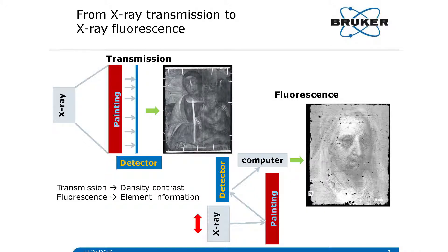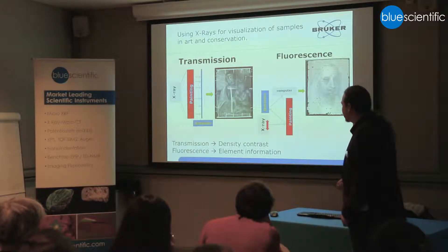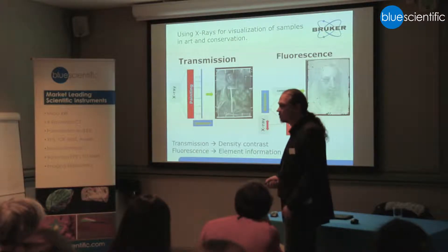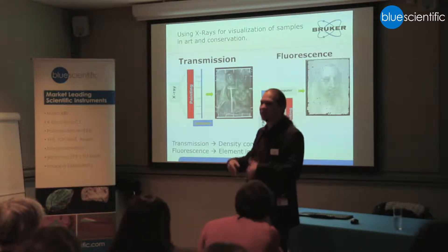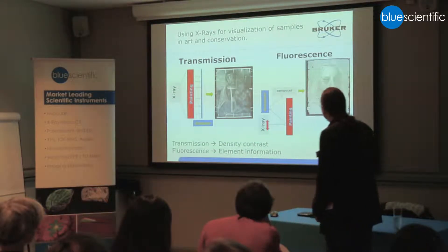What we are doing here is we have an x-ray source that moves over the painting back and forth, focused through the optic part. We have a detector which is not looking at the other side but looking at what is coming from the sample itself. In the computer, it generates a fluorescence image. The difference between transmission and fluorescence imaging is that we really get elemental information — not just density information but truly elemental.